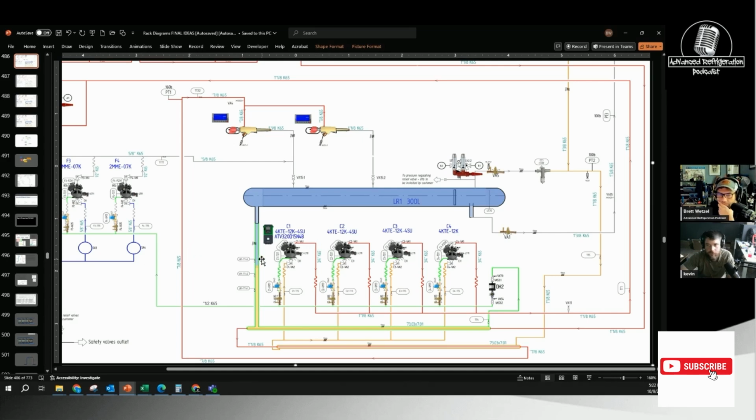It's really close to that. All right, so we're running around 36 degrees saturated, so that means that oil is going to be super, super cold. And as we all know, CO2 is extremely miscible with the oil. So the oil is going to sit down in the bottom of this flash tank and get redistributed over here. But before that, that's why we take this discharge line and run it through this heat exchanger to warm up the actual oil.